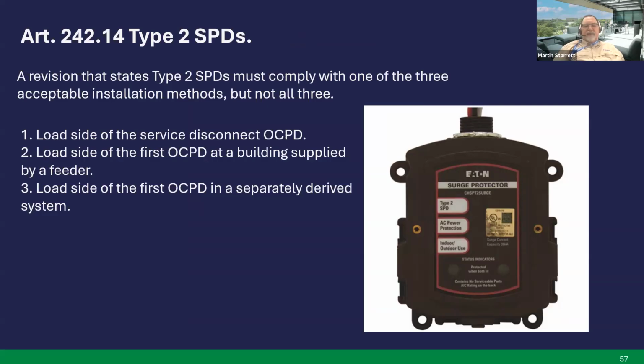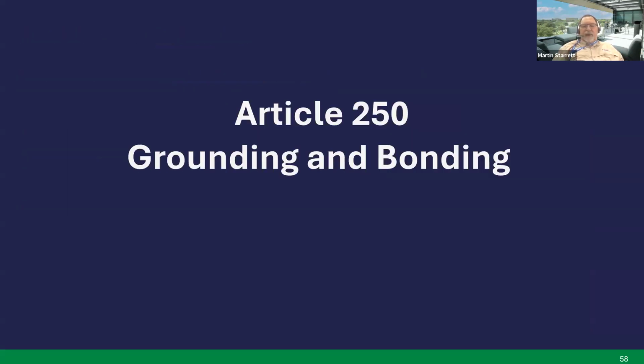242.14, Type 2 surge protection devices. The revision states that Type 2 surge protection devices must comply with one of the three acceptable installation methods, but not all three. In 2023, the way it read, you would have to meet all of them. But they've cleaned that up and just say you only have to do one of the three. That would be either the load side of the service disconnect overcurrent protective device, the load side of the first overcurrent protective device at a building supplied by a feeder, or the load side of the first overcurrent protective device in a separately derived system. So now you only have to do one of these. Next slide. Article 250, grounding and bonding.